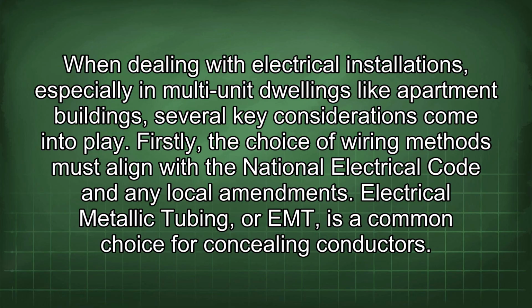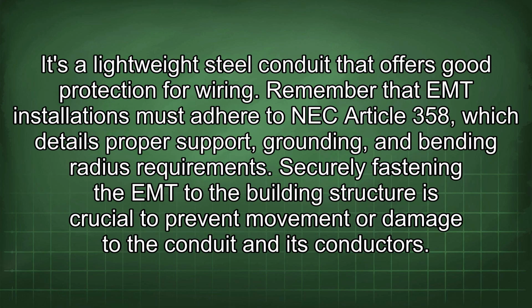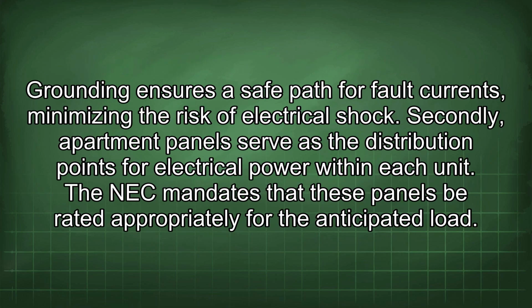The electrical metallic tubing, or EMT, is a common choice for concealing conductors. It's a lightweight steel conduit that offers good protection for wiring. Remember that EMT installations must adhere to NEC Article 358, which details proper support, grounding, and bending radius requirements. Securely fastening the EMT to the building structure is crucial to prevent movement or damage to the conduit and its conductors. Grounding ensures a safe path for fault currents, minimizing the risk of electrical shock.